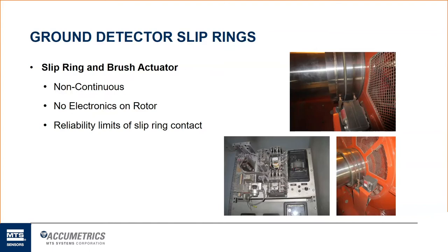So there's no electronics on the rotor. It's non-continuous. You obviously have the reliability limits of a mechanical connection of those brushes touching on that slip ring. They need to be replaced at least once a year, a couple times a year. We run into a lot of customers where that solenoid doesn't work anymore. It's not making a good connection, and there's no feedback to tell them whether there is a connection or not. You can see the receiver part of the electronics is very old. This system was probably designed and developed in the 50s or 60s. So it goes back a very long time, and there's almost no serviceability of this. Customers can't find support for this product.